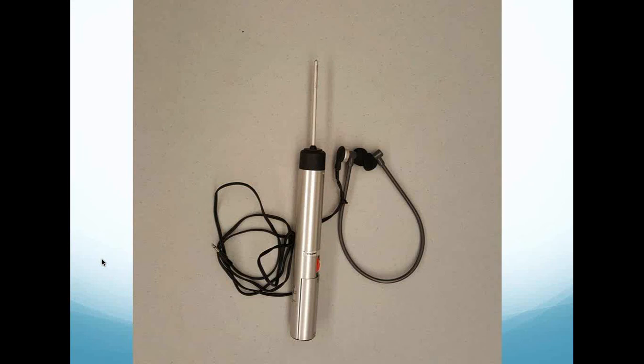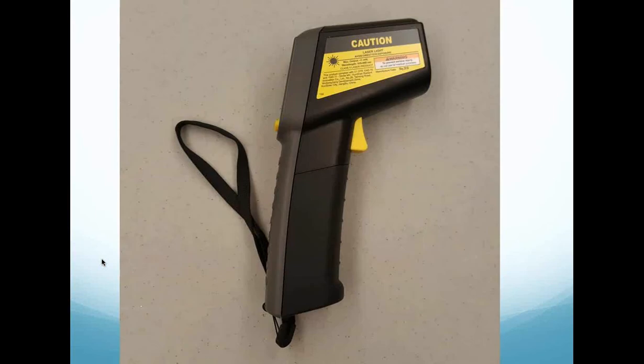In a bellows-style bimetallic thermostatic trap, I need you to be very patient when you listen to those with an ultrasonic listening device. It's going to take a bit, because you want that device to cycle. It may take a bit for that steam to come through. It will shut the trap off, it will cool, and then the element of that thermostatic trap will open. So you need to understand how these traps actuate, and you need to be a little bit patient as you listen to them and evaluate them. A thermodynamic disc trap is very easy to listen to and hear. So is an inverted bucket steam trap. Those are very, very easy to listen to and hear with these devices.